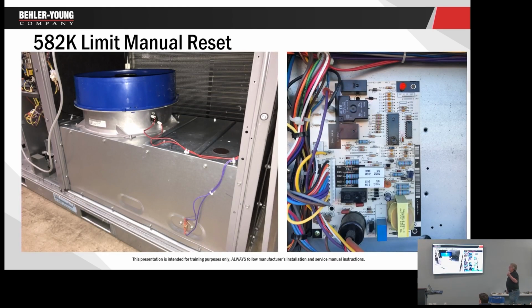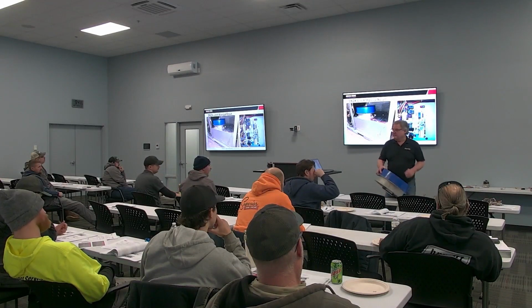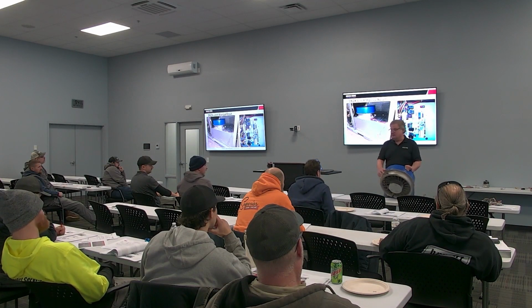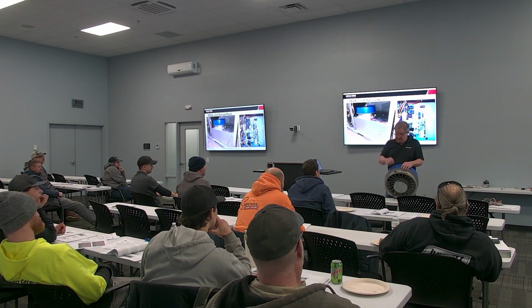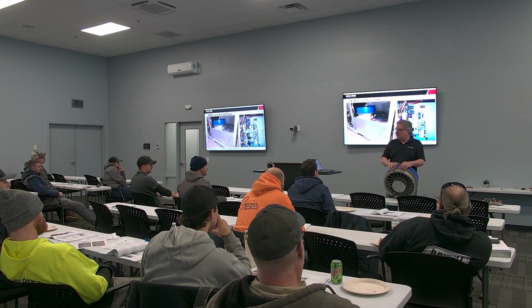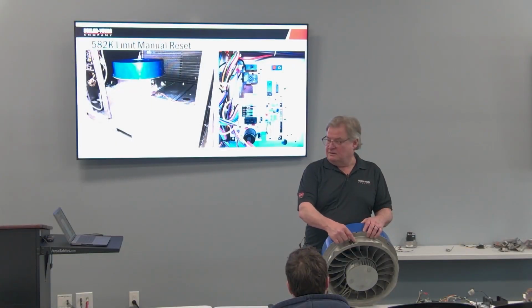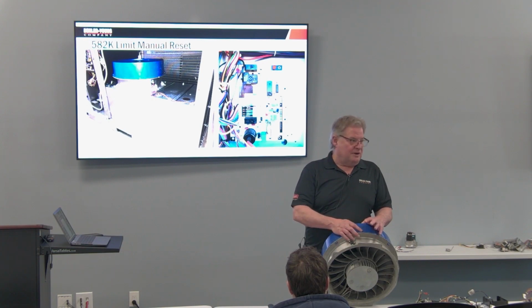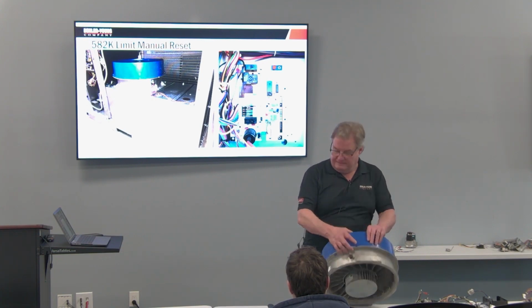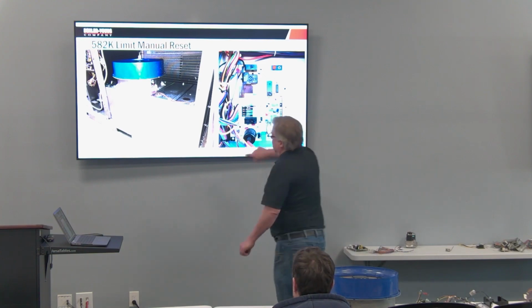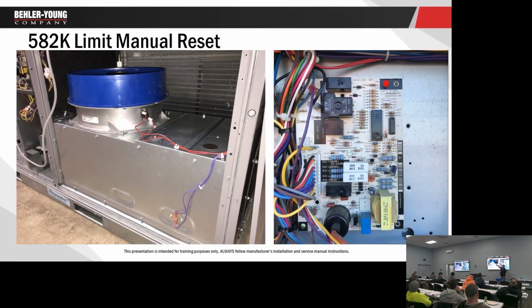Okay. A few more things on this and we'll take a break. We're going to finish up this Axion motor. So if you rewind to about 2019, on the side of our blower motor, there's a limit here, which is still here. This was manual reset, and this one is actually manual reset. So that red wire that goes to that safety circuit, it used to go right here. So if you have a red wire in a Bryant rooftop unit, what is it? 24 volts, right? Limits are purple. 24 volts is red.